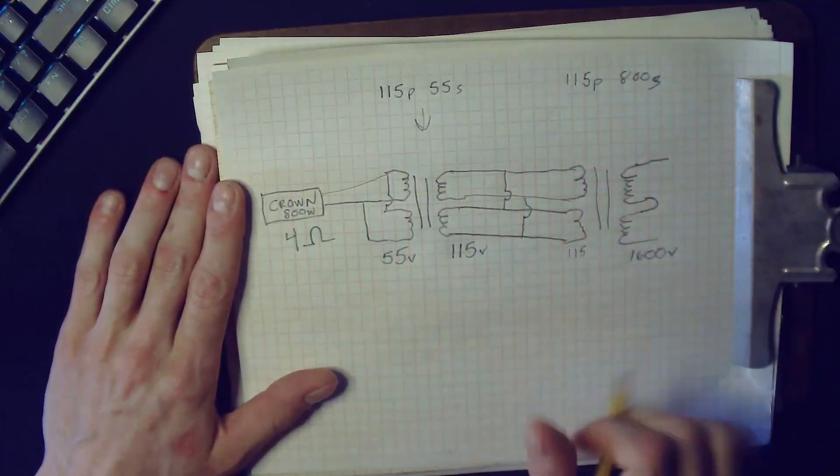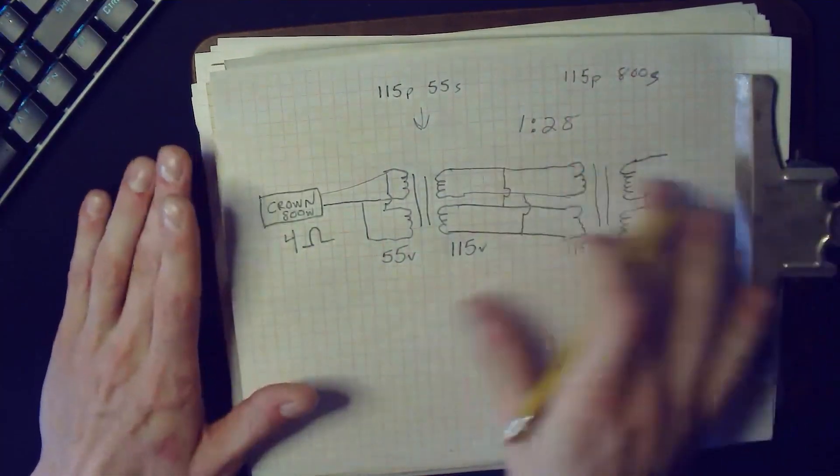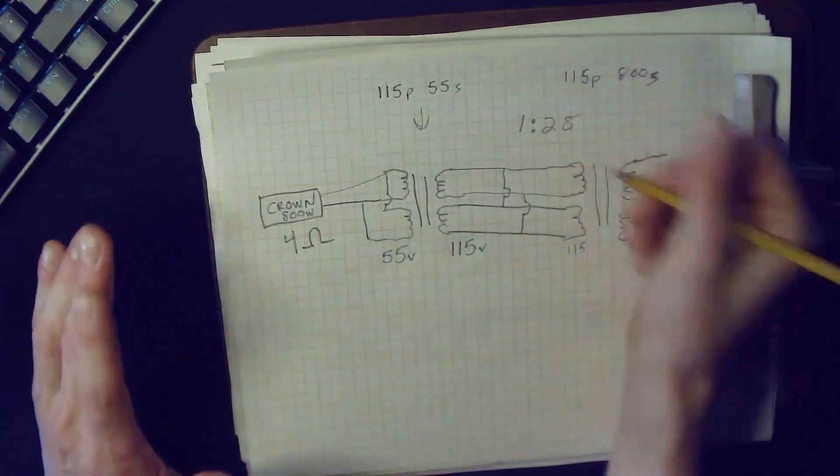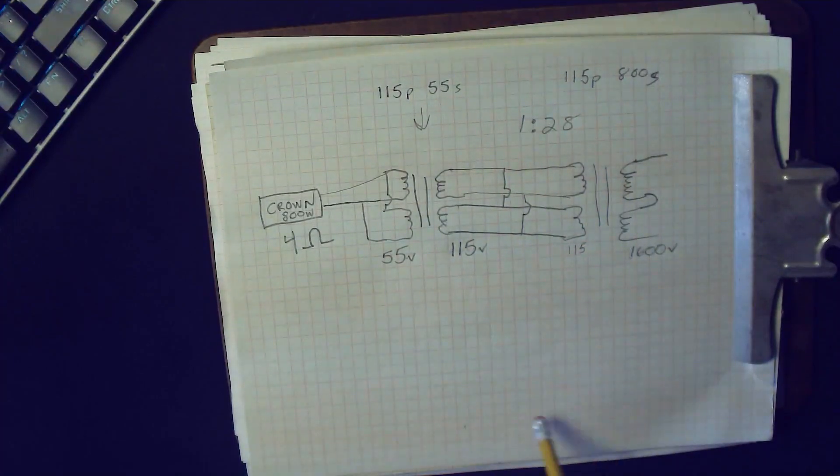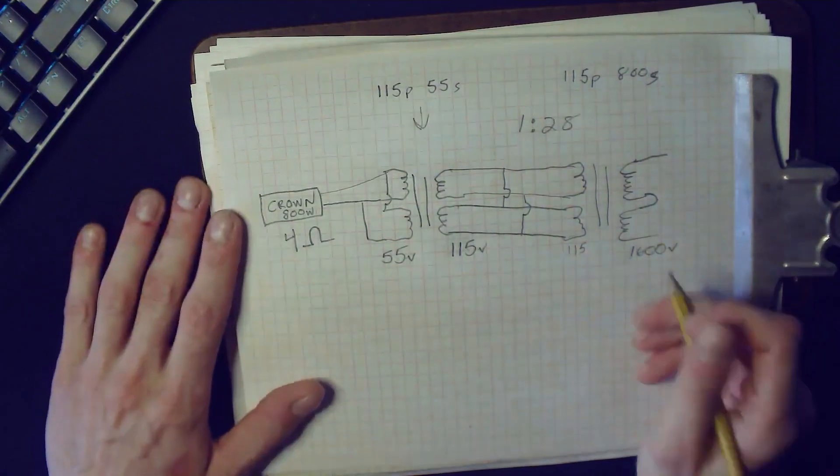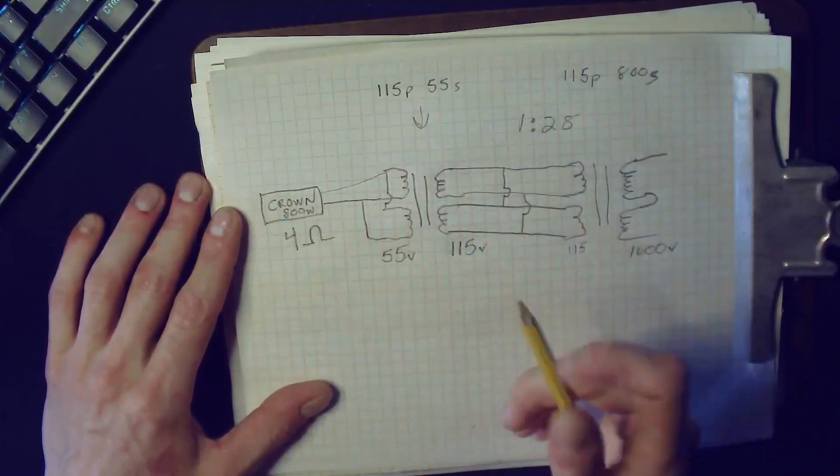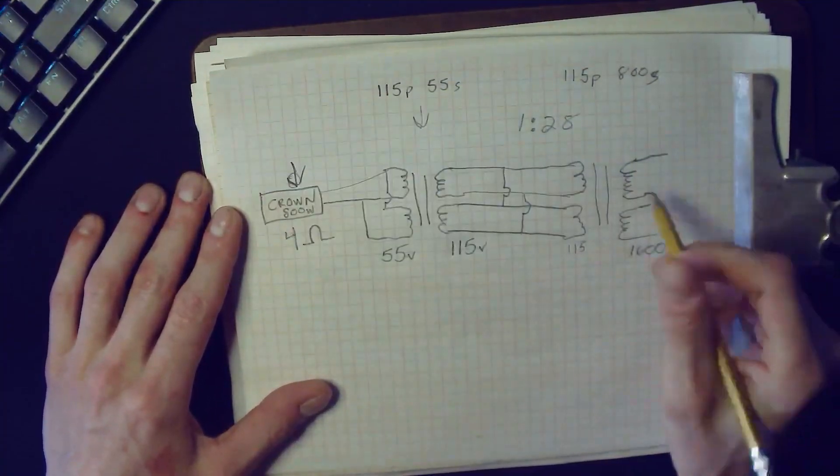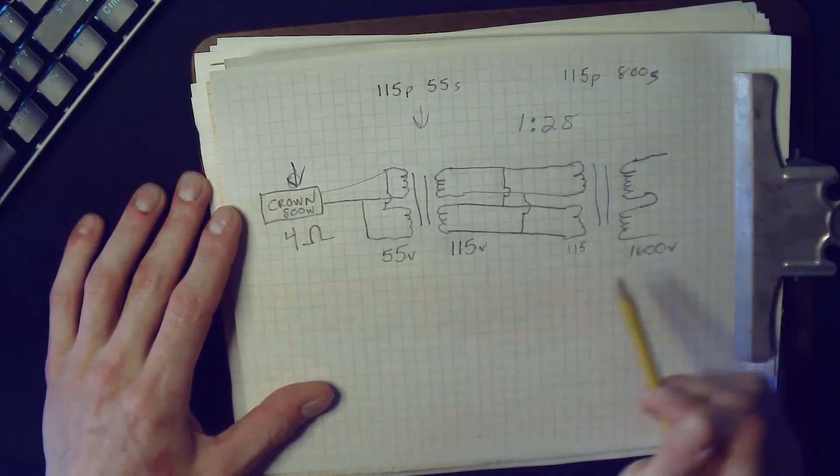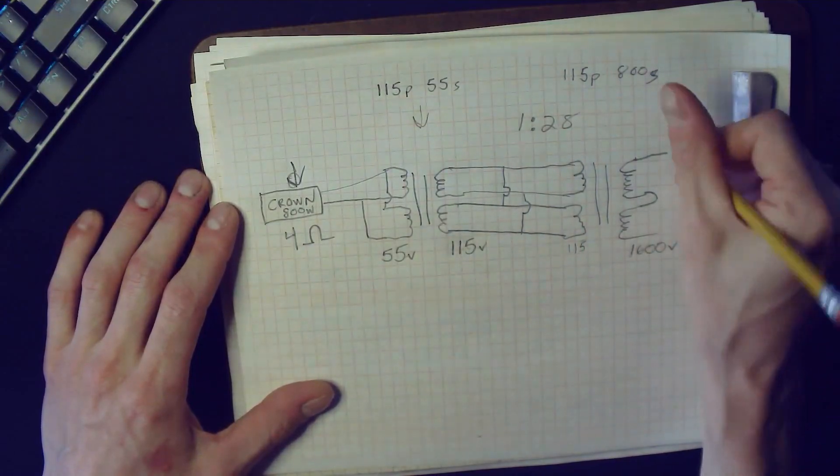So now this is a 1600 volt winding. That ratio, 55 to 1600, is not exactly perfect but somewhere around a 1 to 28 turns ratio, somewhere in there, maybe 1 to 29. It's close to our 1 to 27.3 turns ratio that we want. It's very close. It works.